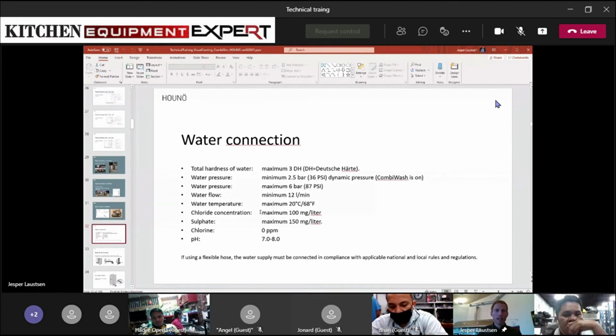It's not only lime scale that we need to prevent by having some supplied water using a filtration system. We cannot accept high concentrations of chloride and sulfate that will have a chemical reaction inside the cavity at the stainless steel. And so to avoid that, please insert a water treatment system to eliminate this. And for the chlorine, some in the past have used chlorine to clean the oven. That's a very, very bad idea, because it will very fast make the oven cavity full of rust. And if it's full of rust, the oven cannot be used anymore, and it's not covered by warranty.